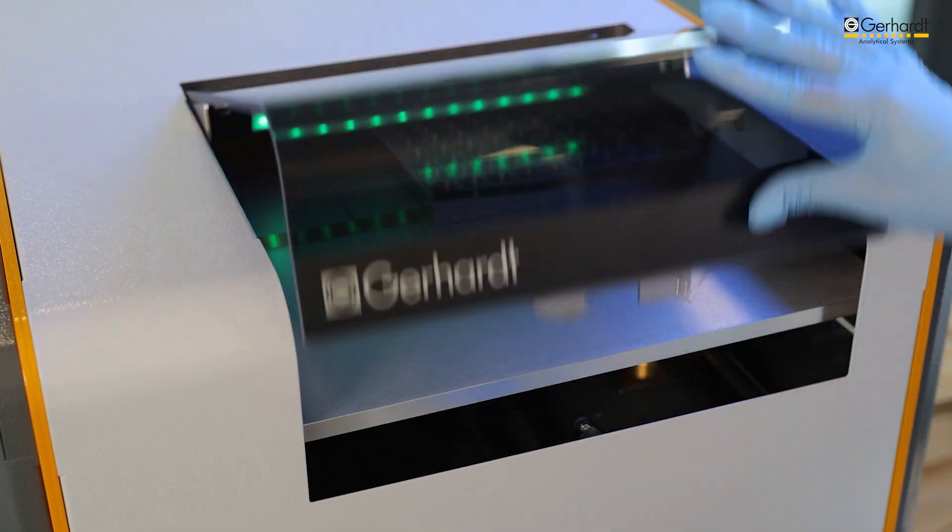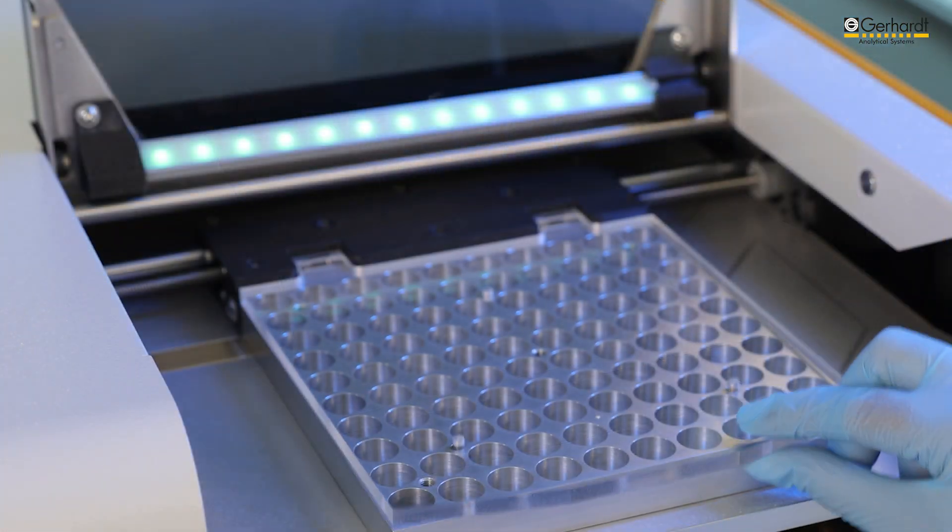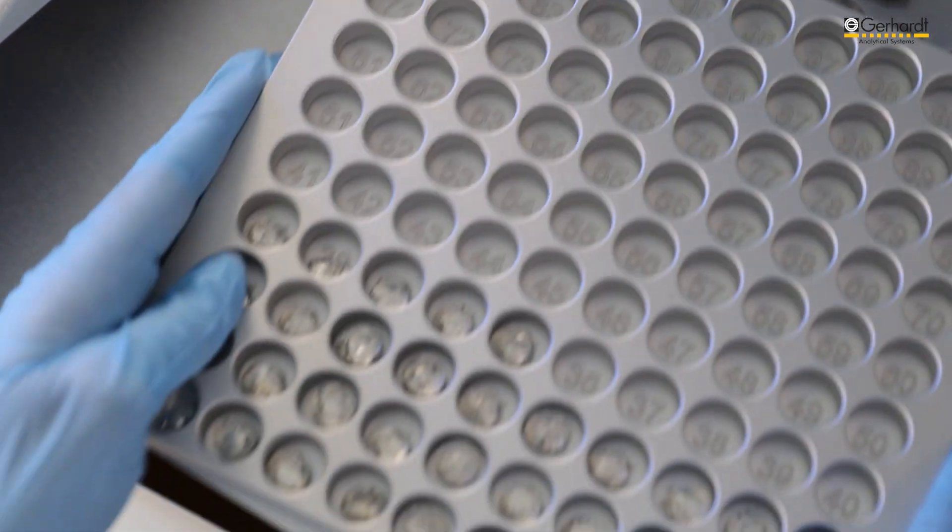Sample sizes from 1 to 500 mg can be analyzed without any problem. Thanks to innovative total gas analysis, even very low contents can be determined precisely.